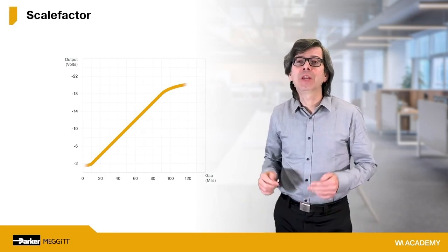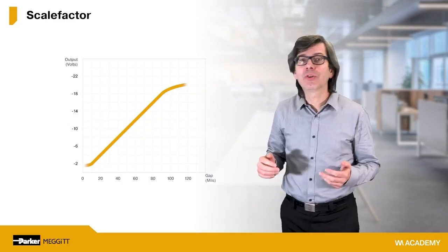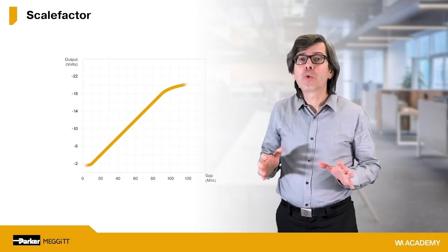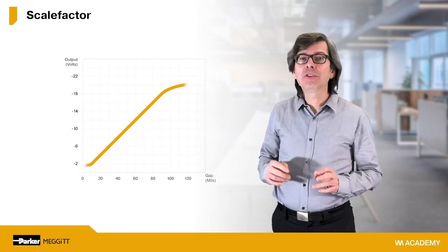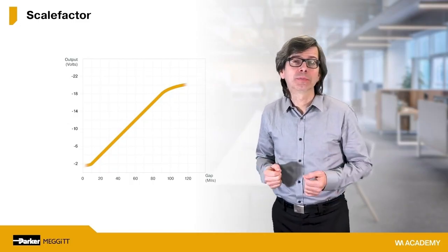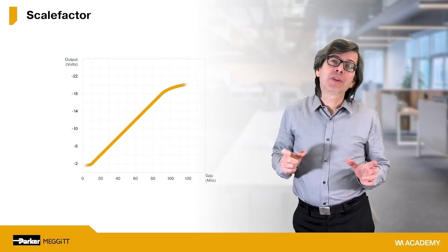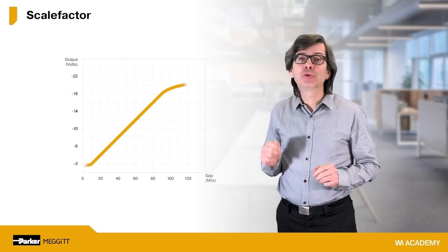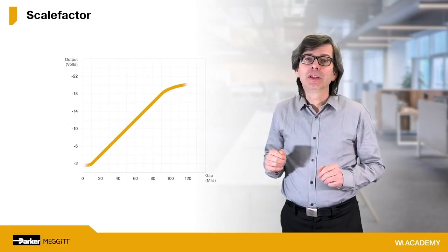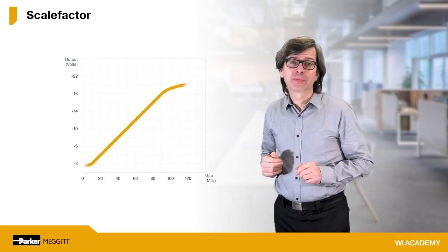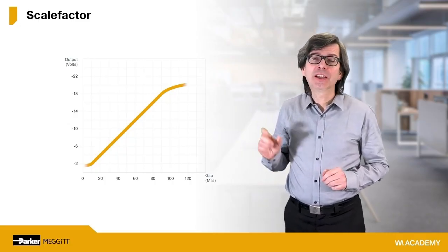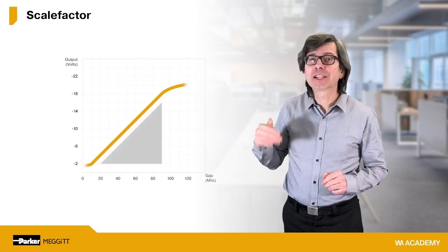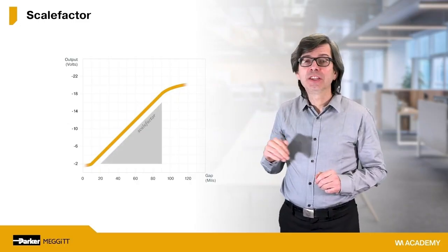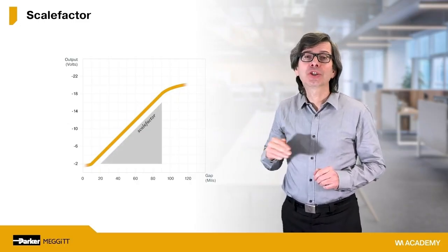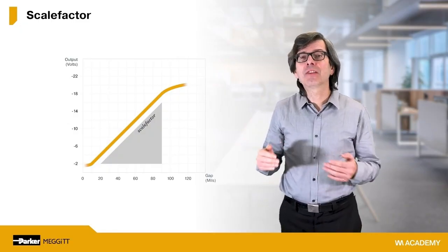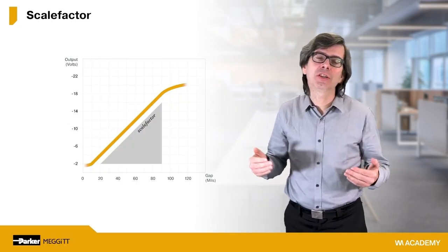But in practice, you will need to be able to work in either system of measurement. And depending on where your customer is located, they may be using imperial units or metric units. The scale factor we have chosen for this example is 200 millivolt per mil, since it's the most common in practice. To visualize how this works, let's first employ a triangle. The slope of our yellow line is the scale factor. For a given horizontal distance on the graph, the scale factor implies a given change in the vertical direction.